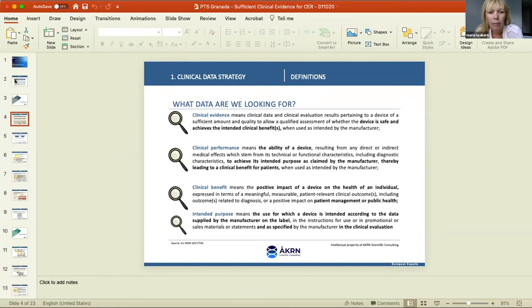Clinical performance is the ability of the device, resulting from any direct or indirect medical effect which stems from its technical and functional characteristics, including diagnostic characteristics, to achieve the intended purpose as claimed by the manufacturer, thereby leading to the clinical benefits for the patient when used as intended by the manufacturer. So again, you have to define your intended purpose to know how you are going to design and evaluate your clinical performance.